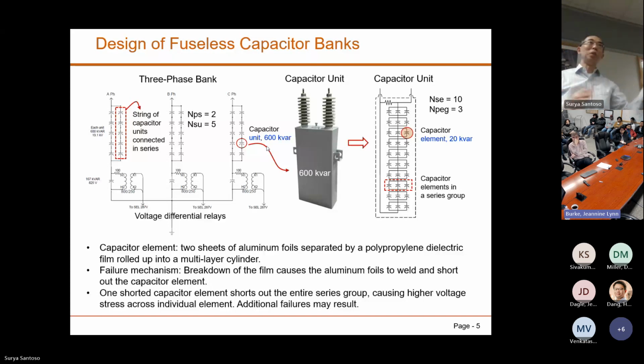There is another type of capacitor bank, the fused capacitor bank, but fused capacitor banks are very old technology. The fuseless design is relatively new, maybe in the sense that it is already 30, 40 years old. For fuseless capacitor banks, when they fail, they fail shorted, whereas for fused capacitor banks, they fail open. So whatever I do for this machine learning development for the fuseless capacitor bank will not be applicable to the fused capacitor bank. You have to design a different machine learning because the failure mechanism is not the same.